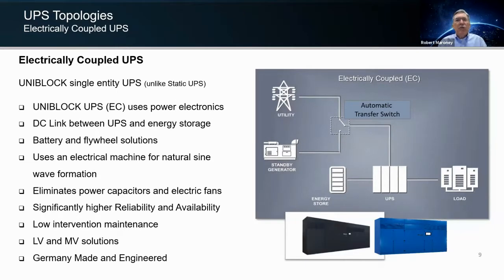So when you look at the Piller rotary UPS, or what we call a Uniblock, okay, electrically connected is for the most part in the United States, okay. You have genset and utility connected to an automatic transfer switch, we have a DC bus between the energy storage and our UPS, and that can be battery, any battery you choose, or mechanical. We call it kinetic energy storage or flywheel energy system. But one of the benefits here is that we're not using capacitors and fans, and we're not using multi-modules. It's a single module system in total. It's also available in low voltage and medium voltage, so it takes us into a lot of different applications. And that allows us lower interventions and things like that.